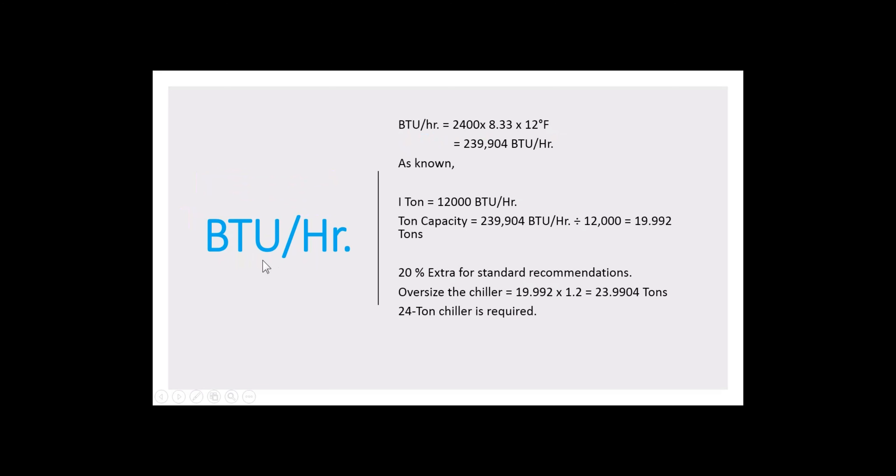Let us find out British thermal units per hour. Just apply the given values in the formula. Q is 2,400 gallons per hour times 8.33 times 12 degrees Fahrenheit which we calculated. Once you multiply these numbers, you can get 239,904 British thermal units per hour.